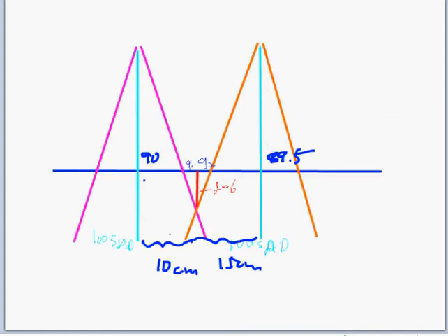So even in this very complicated looking situation, it again is just a very simple geometry problem. We would just take our jaw setting, which is 10 divided by 100, and 15 divided by 100, multiply it by our depth, and that gives us our two gaps. So again, like I said, these look more complicated than they are, but if you just know some basic geometry, they're actually very straightforward problems.